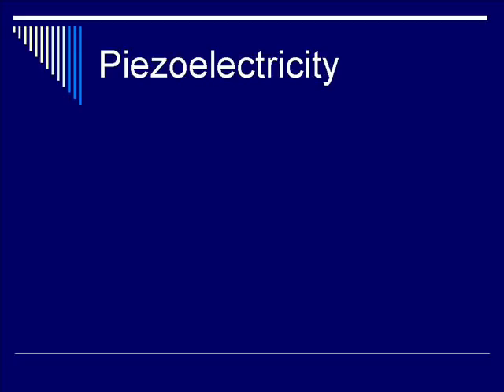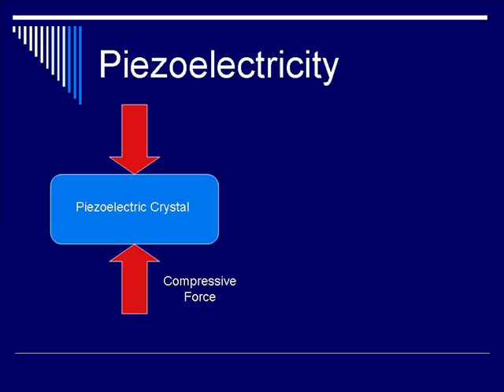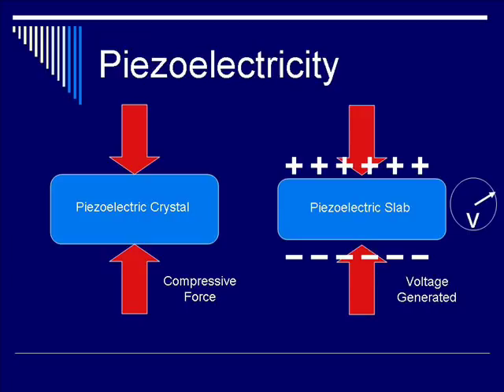Piezoelectricity — what is it all about? This phenomenon was discovered by the Curie brothers. In response to a compressive force exerted on a piezoelectric slab, a net electric dipole moment results, meaning a voltage is measured across it due to the strain. In medical ultrasound, this voltage is formed due to acoustic oscillation. A piezoelectric crystal experiencing a compressive force shows a voltage across the slab, with positive and negative charges on opposite sides, with a specific voltage characteristic of the thickness and type of that slab.